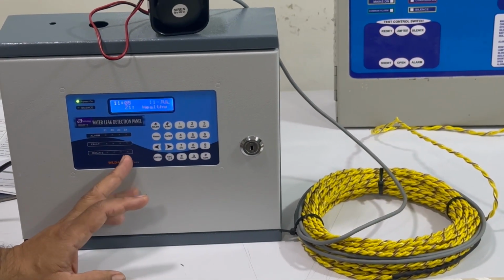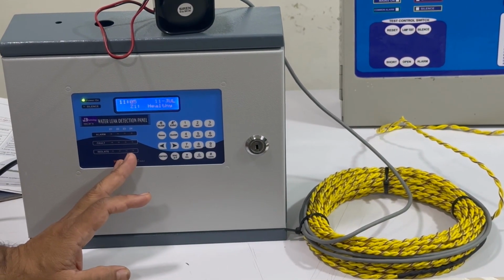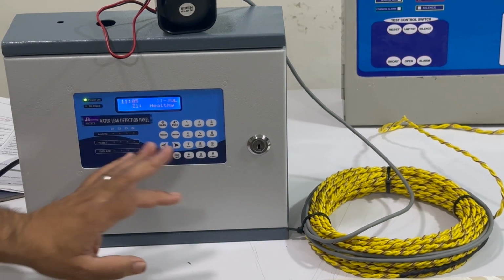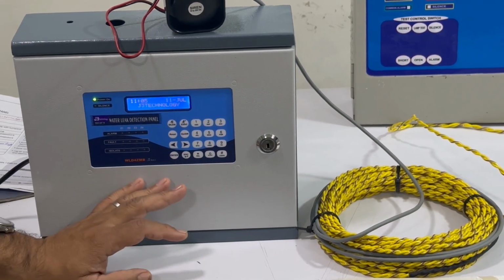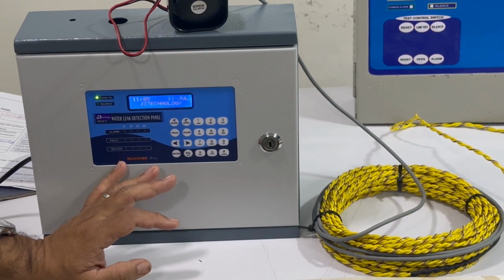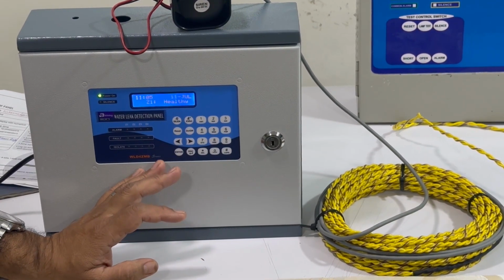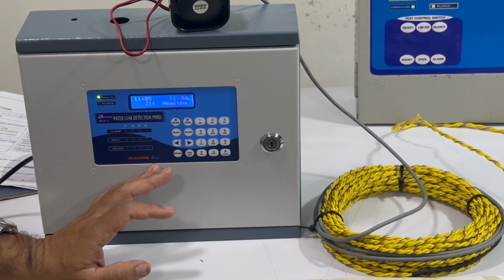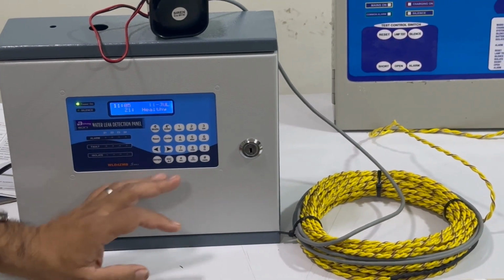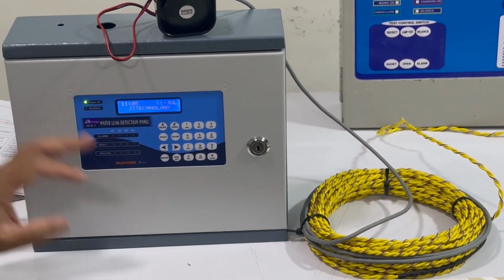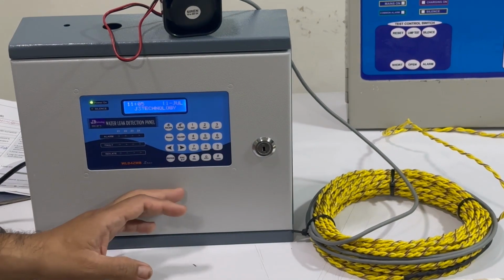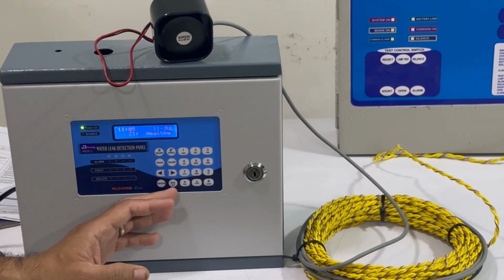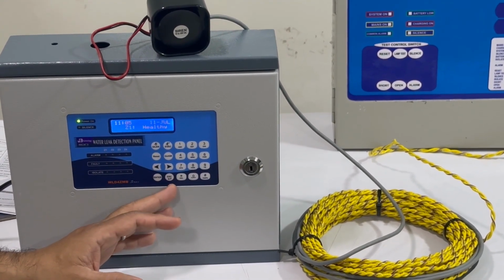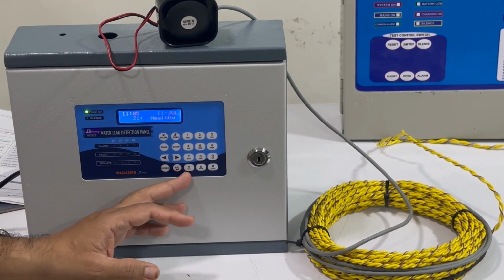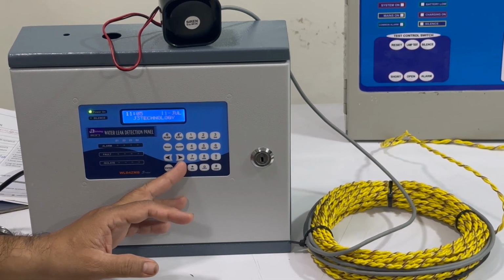Zone names can be configured. The device can be accessed remotely by BMS; you can access this panel remotely via the Modbus protocol. It logs an extensive variety of events and alarms. It is standalone with integrated leakage detection and notification. It pinpoints the zone of a leak quickly and accurately, and gives detailed alarm history with time and date for troubleshooting.